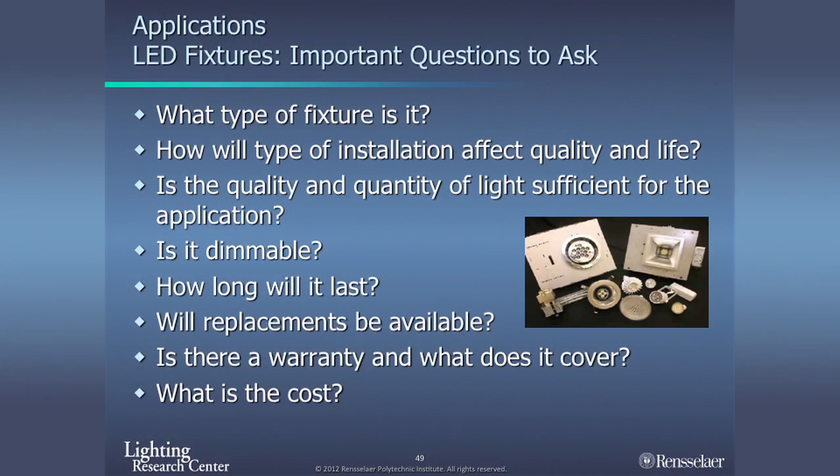So when you're thinking of questions, what type of fixture is it? Is it going to be enclosed? Is heat going to be an issue? What's the type of installation? Is it going in a ceiling where the plenum's going to be very hot? Is the quality and quantity of light going to be sufficient?